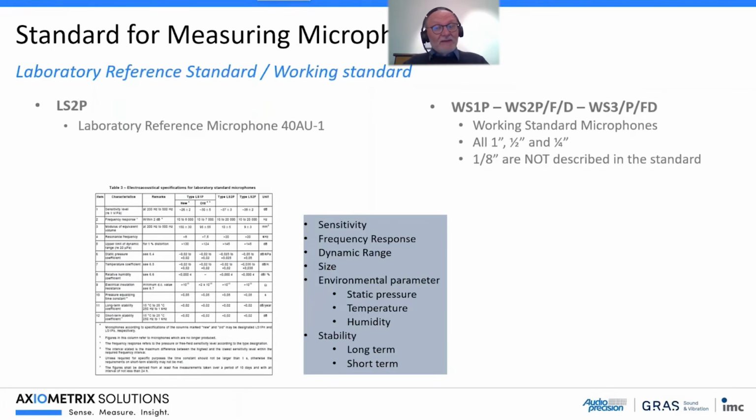1/8 of an inch microphones are actually not described in the standard, but the manufacturers of 1/8 of an inch microphones make these microphones according to the standard. So it means that the size is according to the standard. The sensitivity is described. So they're actually using all the parameters for describing the microphone.